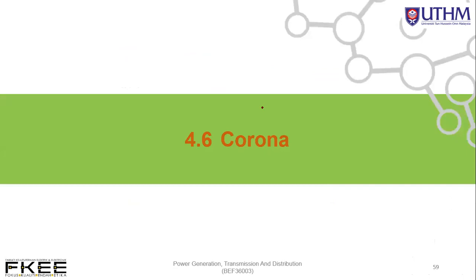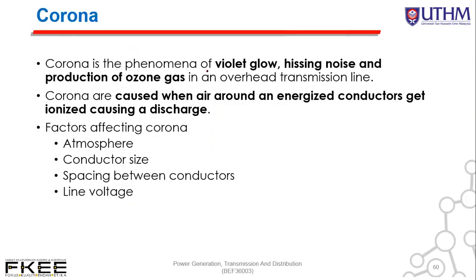Now we look at the case of corona. Corona is the phenomenon of violet glow, hissing noise, and production of ozone gas in an overhead transmission line. Corona is caused when air surrounding the energized conductor gets ionized, causing a discharge. Factors causing corona are: atmospheric conditions, conductor size, spacing between conductors, and line voltage.